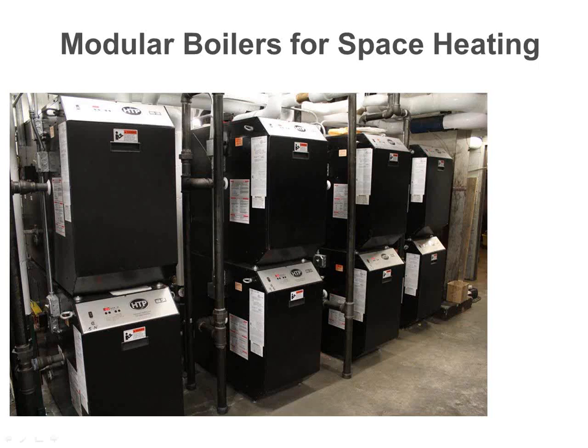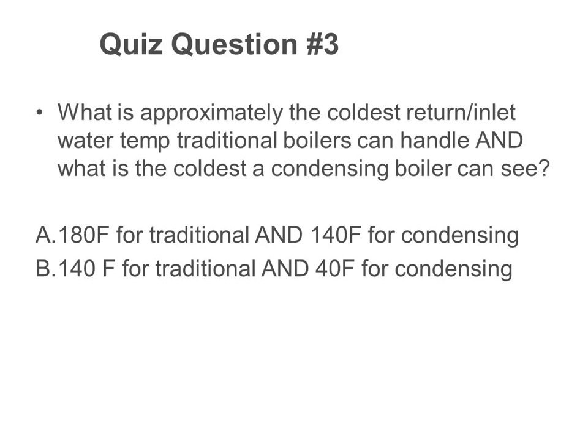There's lots of different ways that you can do that. And saving space is typically a key factor in some of these mechanical rooms. If we can get you the required amount of BTUs in less space, it's usually a good thing. All right, let's launch our third question for you guys here. What is approximately the coldest return water temperature we can have to a traditional boiler, and what is the coldest water we want to see at a condensing boiler?